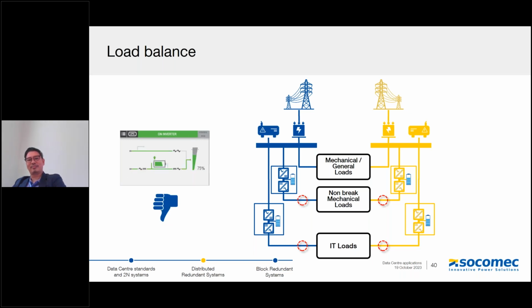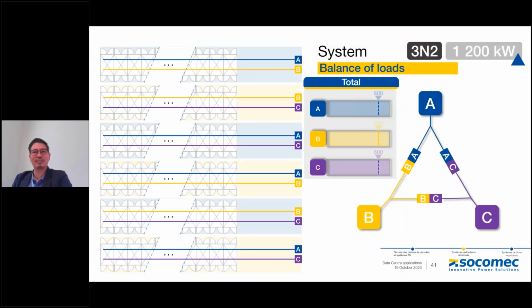But once it goes above 50%, that's where your problem is, because the other UPS will not be able to handle the full load. That's the problem with 2N. So you maintain at 50%, and this gets even more complicated as we go on with 3N.